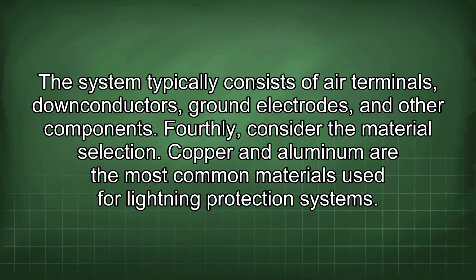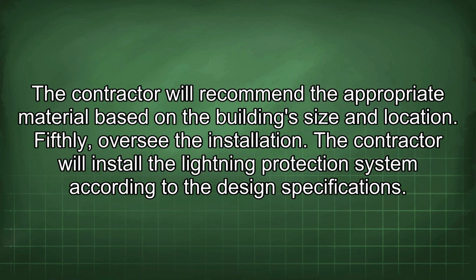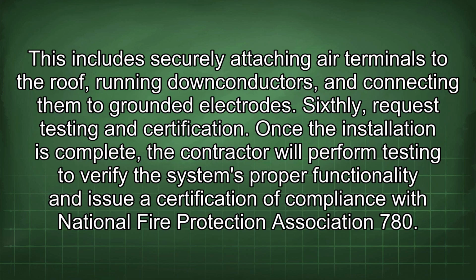Fourthly, consider the material selection. Copper and aluminum are the most common materials used for lightning protection systems. The contractor will recommend the appropriate material based on the building's size and location. Fifthly, oversee the installation. The contractor will install the lightning protection system according to the design specifications. This includes securely attaching air terminals to the roof, running down conductors, and connecting them to grounded electrodes.